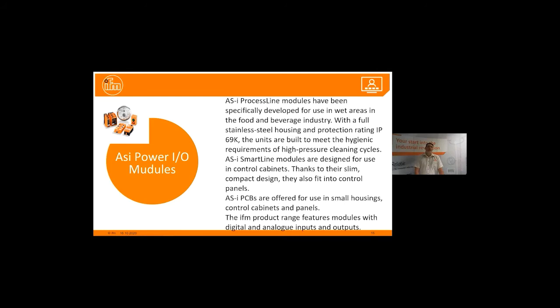The ASI process line module has been specifically developed for use in wet areas, the food and beverage industries, with a full stainless steel housing and protection rating IP69K. The units are built to meet the hygienic requirements for high-pressure cleaning cycles. ASI smart line modules are designed for use in control cabinets. Thanks to their slim, compact design, they also fit into control panels.